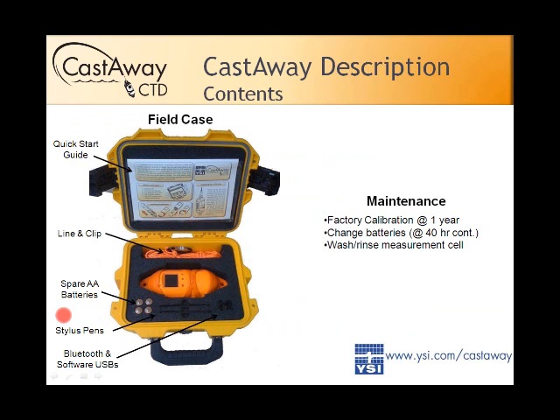The field kit follows general YSI philosophy — trying to give you everything you need in one kit. It includes the Castaway and the jacket, a line with a carabiner for casting from the top (50 feet, roughly 15-17 meters), enough for a shallow water cast. There's a quick-start guide and a user manual included on the USB. There are four AA batteries — two go inside, two are spares.